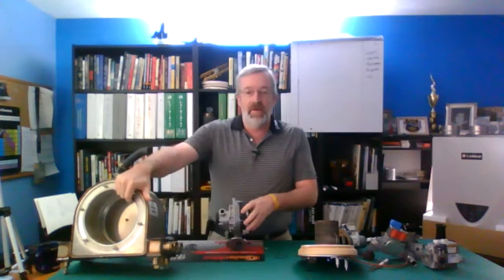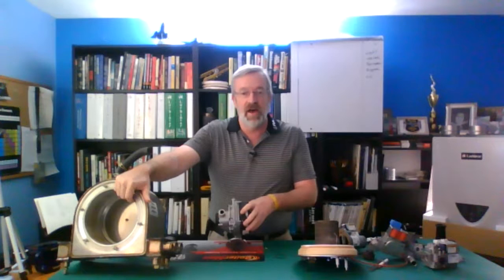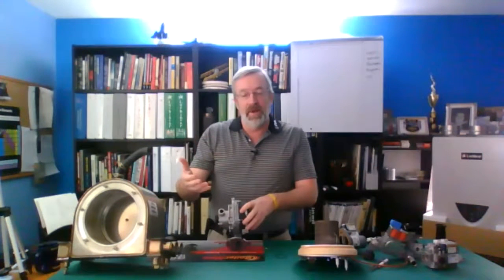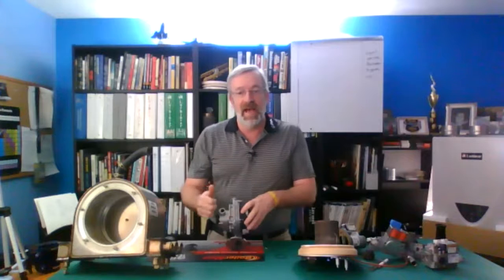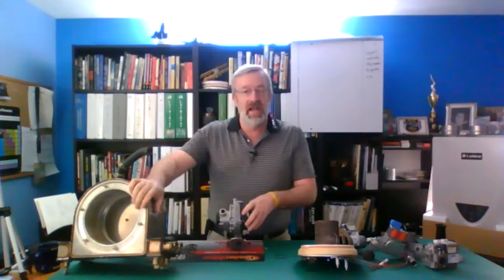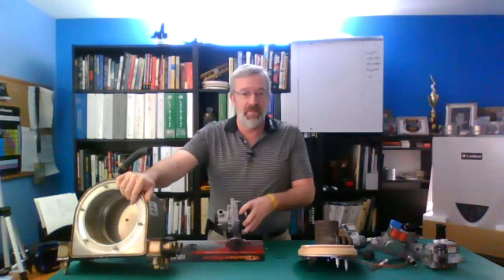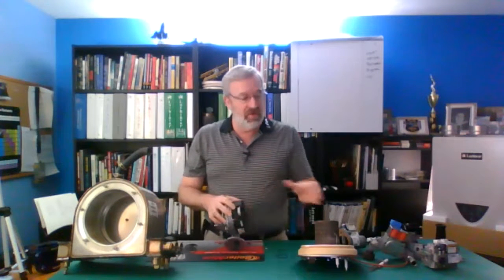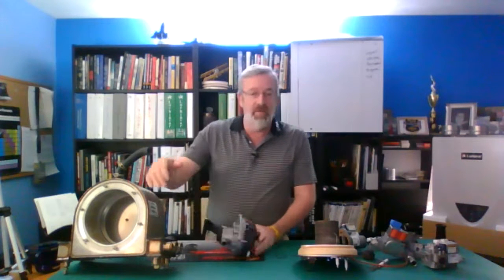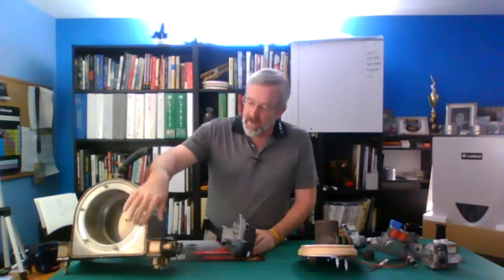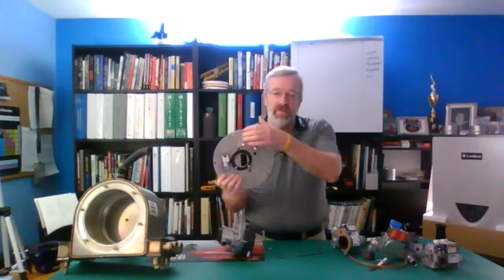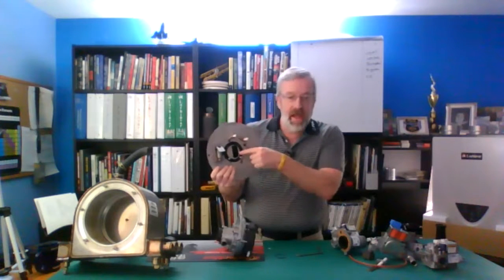When I do that, I'm going to pressurize inside this heat exchanger, and I'll be able to bubble test it without it getting hot. If I light it first, this is going to get hot maybe sometimes before I could see everything with my bubble test. Same on doing the top plate here. So set that. We want to bubble test anywhere we took apart. All of our gas fittings, those sort of things. On here, we'd be looking around the various studs on the heat exchanger top and around our fan. So, go through and just take a look at all of those.